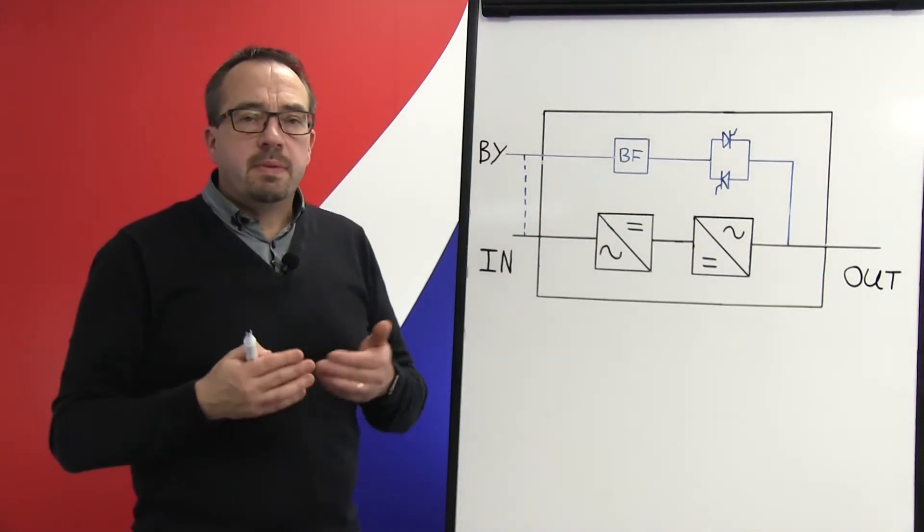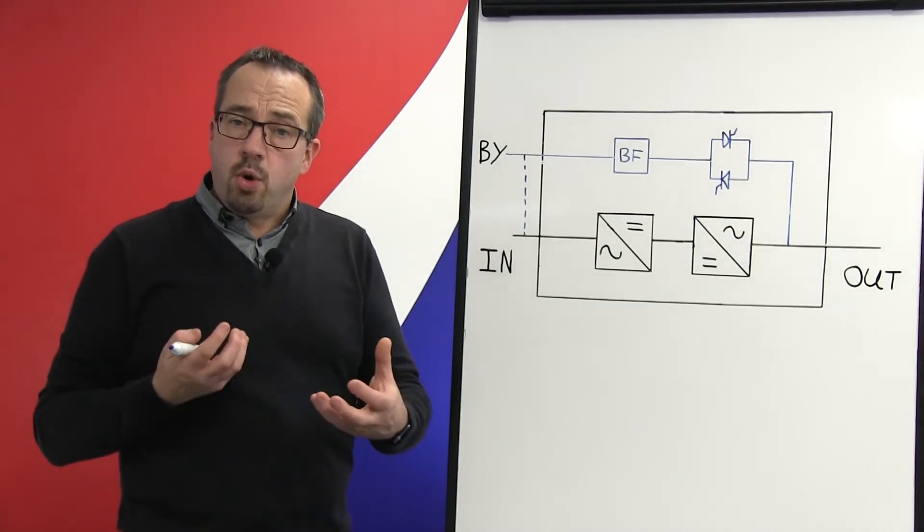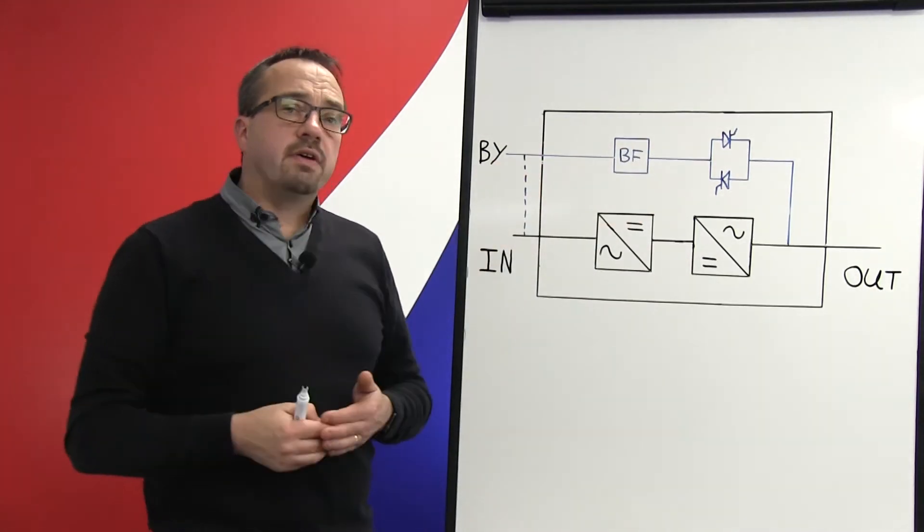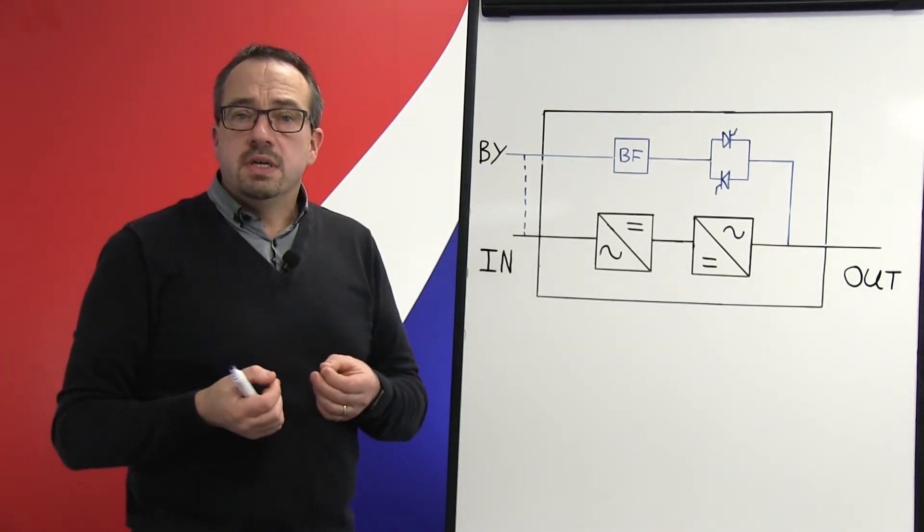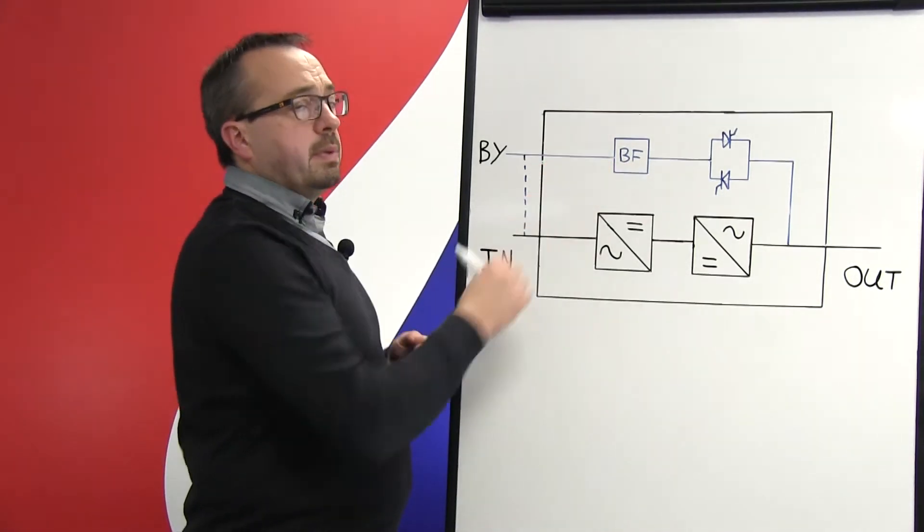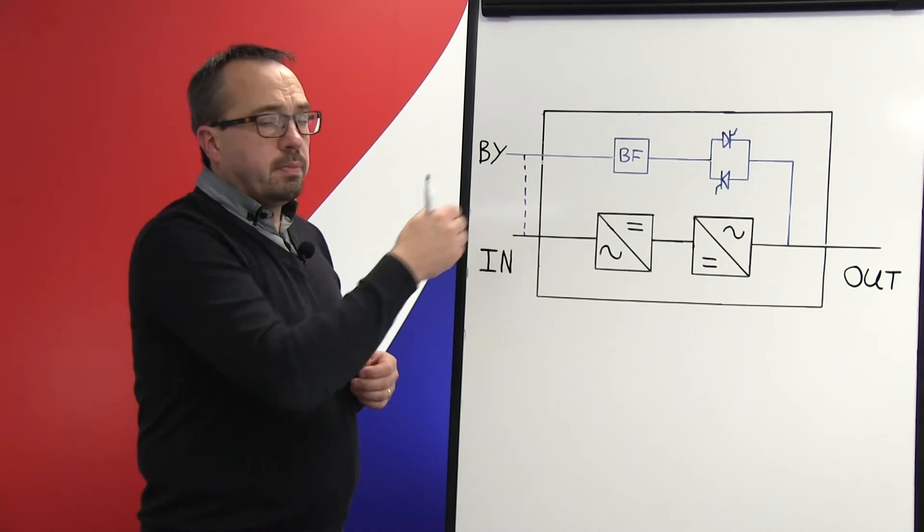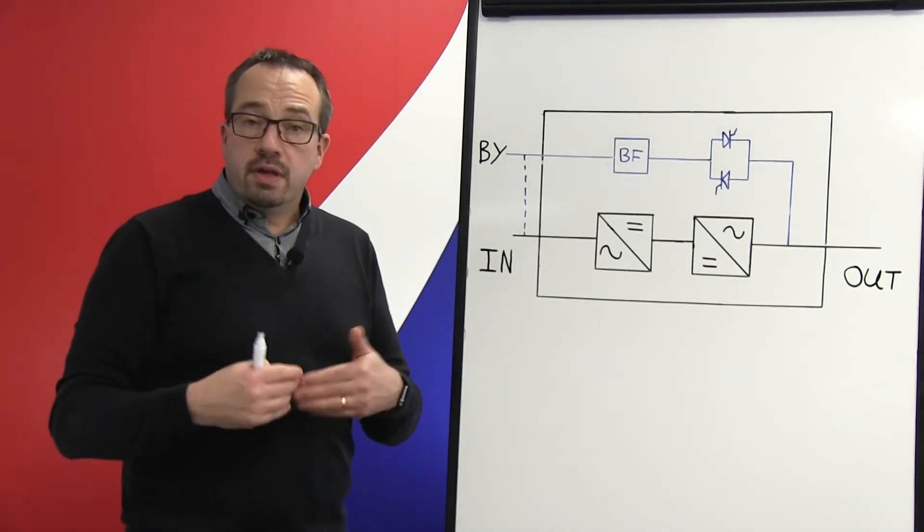The back feed protection device is typically made up of either a contactor which will physically open so we can't pass any current back, or it will be via a current device so that if we measure any current flowing in the bypass line when we are on battery operation, the UPS can take the appropriate action.